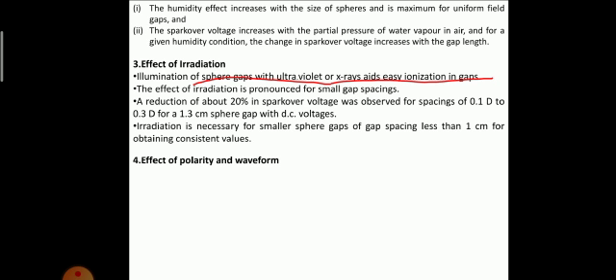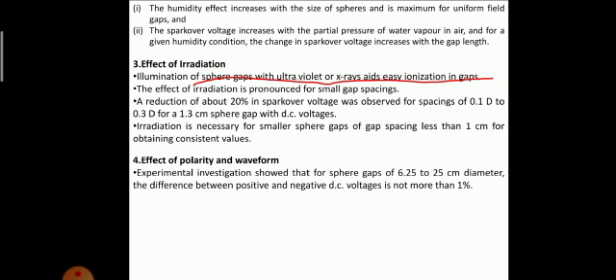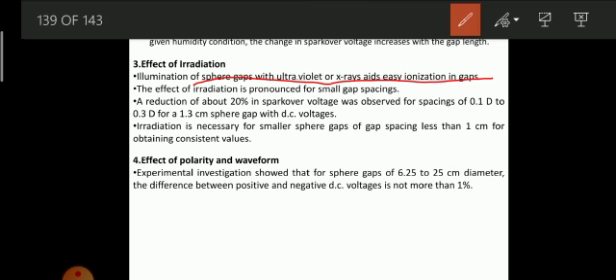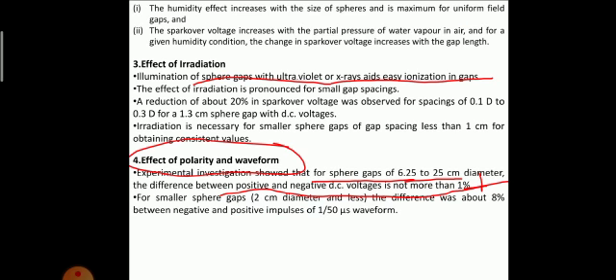Next we will see the effect of polarity and waveform. Now, experimental investigation showed that for sphere gaps of 6.25 to 25 centimeter diameter, the difference between positive and negative DC voltages is not more than 1%. So polarity has an effect, but it was not seen for more than 1%. However, for smaller sphere gaps less than 2 centimeters, the difference was about 8% between the negative and the positive impulses of 1/50 microsecond wave.